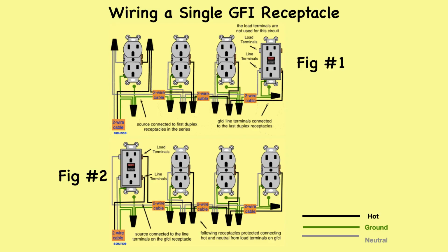In figure number 1, a ground fault circuit interrupter receptacle is added at the end of a row of duplex receptacles for single location protection. The first outlet is connected to the source and 2-wire cable runs from box to box. All wires are spliced with a pigtail at the devices to pass current to the next. The load terminals on the GFCI are not used and it does not protect the other receptacles in the circuit.